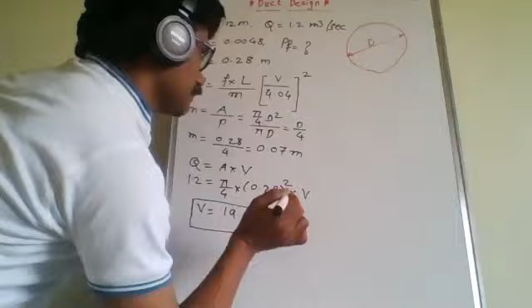Then the discharge Q is given to us. So we know that discharge Q equal to area into velocity, Q equal to A into V. So discharge 1.2 meter cube per second, area that is pi by 4 into d square, velocity that we have to find out. So make the calculations. It comes to 19.48 meter per second. So that is the mean velocity of the air passing through the duct in meter per second.